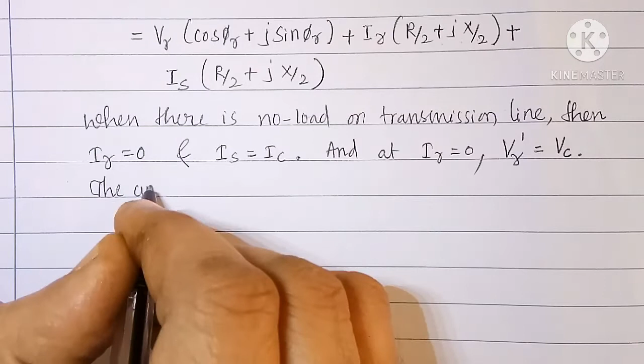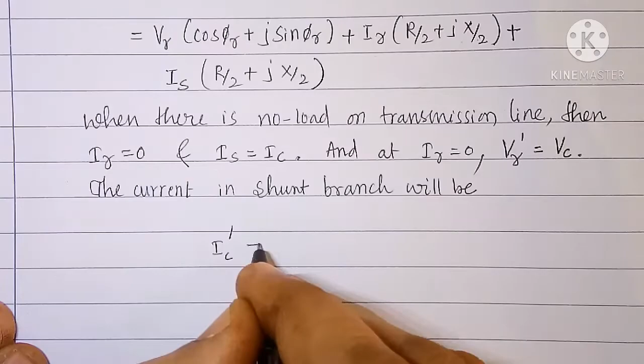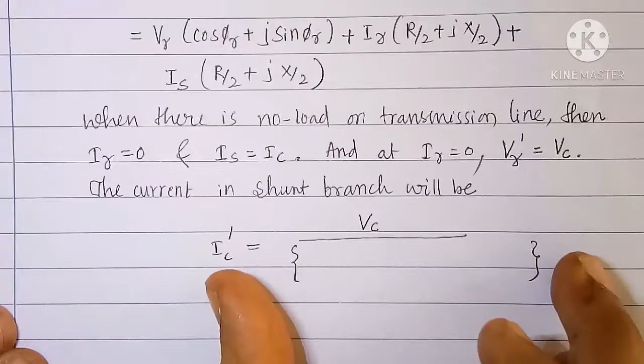The current in the shunt branch will be IC dash. IC dash is the current in the shunt branch, that is the capacitance, when IR is equal to 0. Like we took receiving end voltage as VR dash at IR equal to 0, it is given by VC by the impedance. Which impedance do we have to take here? We have to take the impedance between the sending end and the return path through the midpoint only. That means R by 2 plus j X by 2 minus j of 1 by omega C. This is R by 2 near sending end, X by 2 near sending end, and this is the capacitive reactance between midpoint and return path.